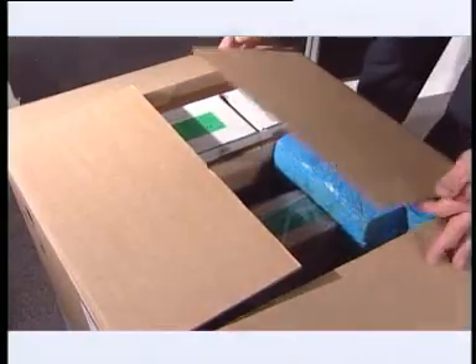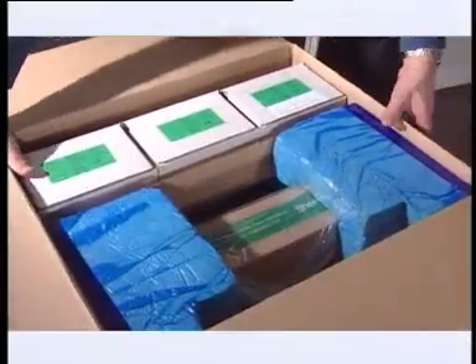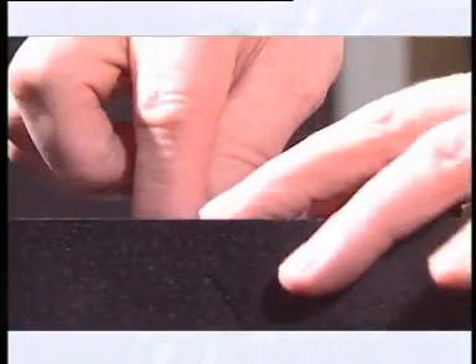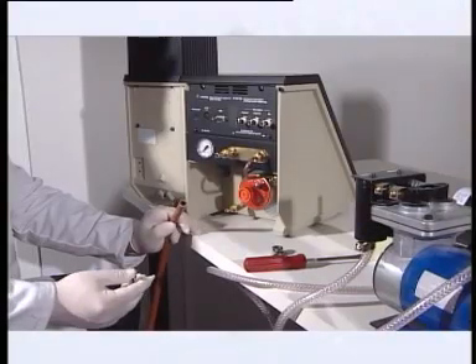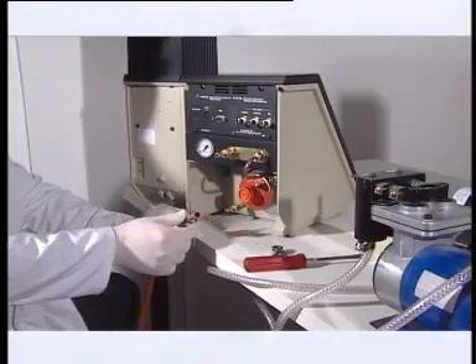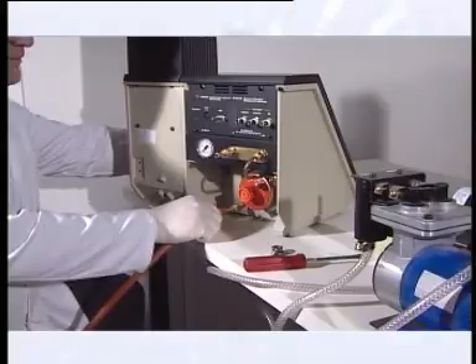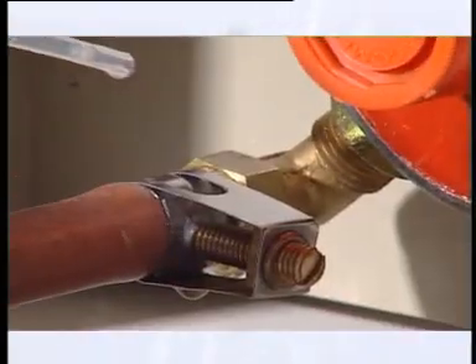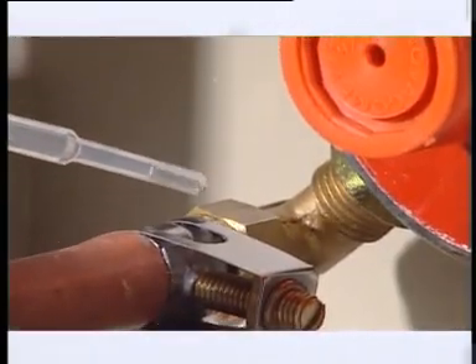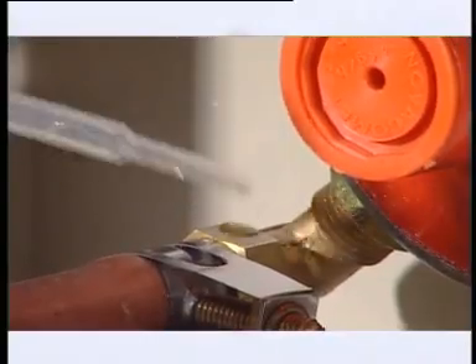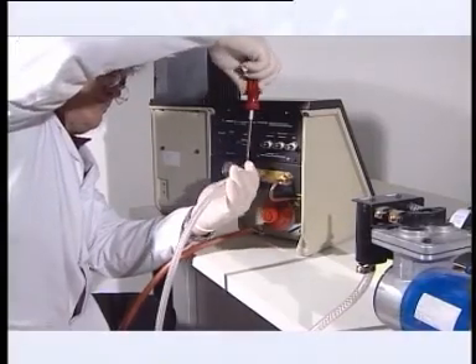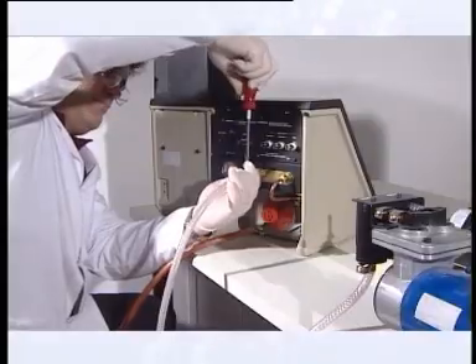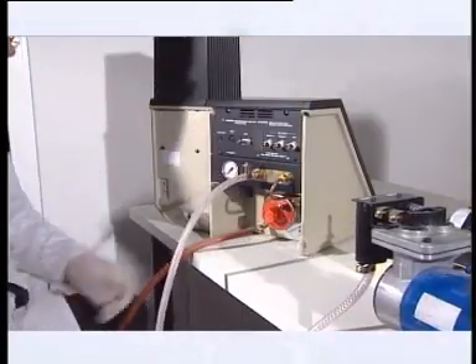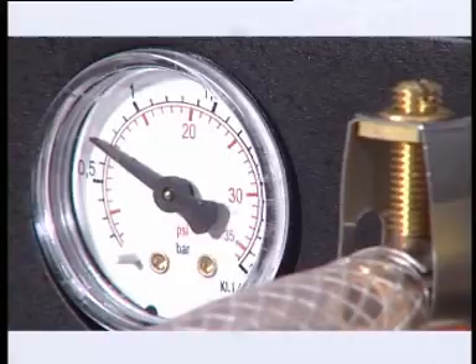After unpacking carefully and checking each item against the packing information in section 2.3 in the operator manual, remove the packing from the glass chimney. The correct regulator, which gives an output of 2 bar, should be fitted to the gas cylinder. Connect the air and gas to the rear of the Model 420 using the connectors supplied, checking especially for gas leaks. The Model 420 works with butane, propane and LPG. It does not work with natural gas due to its variability of pressure and quality.